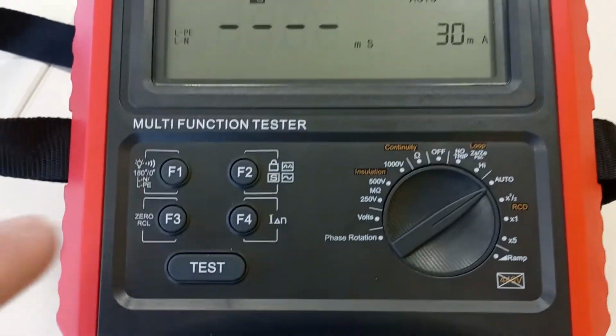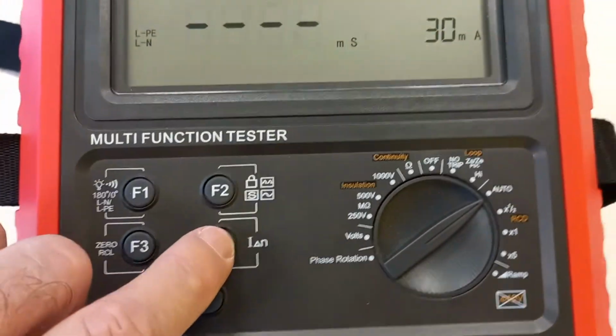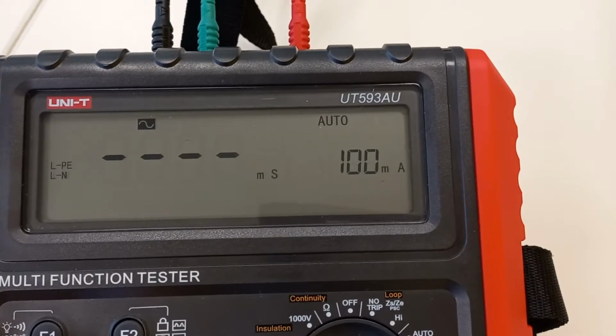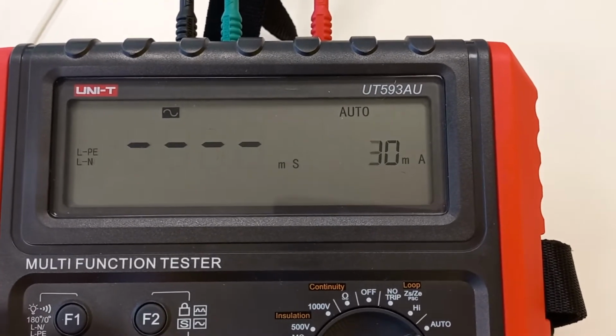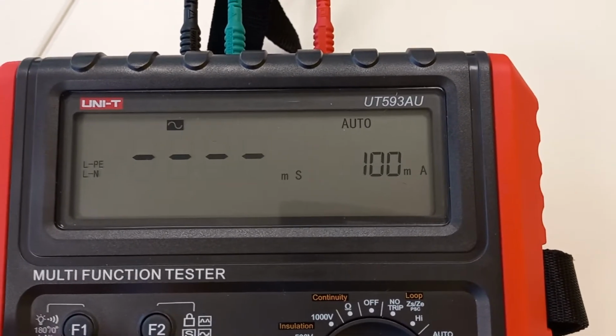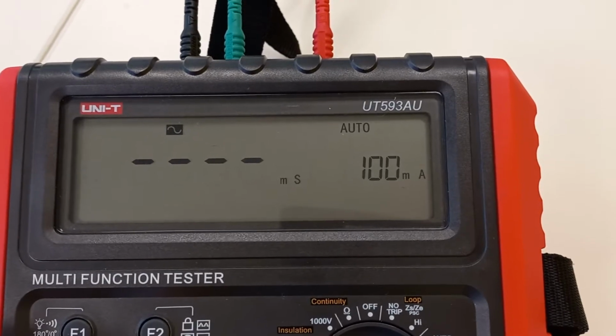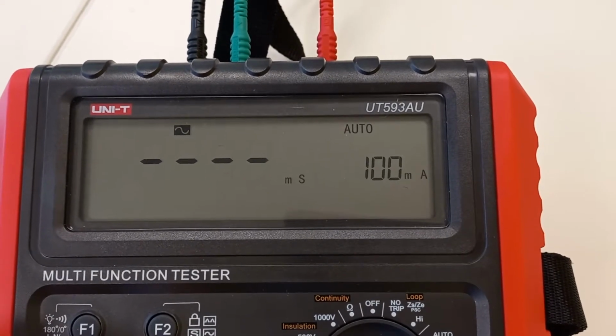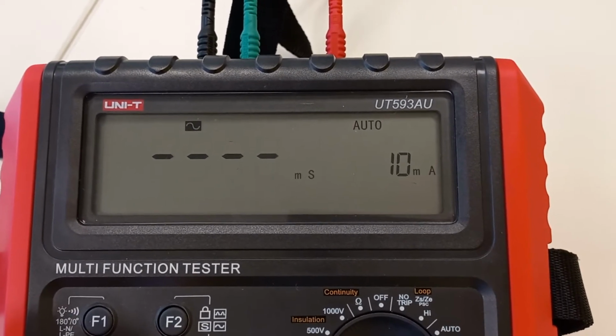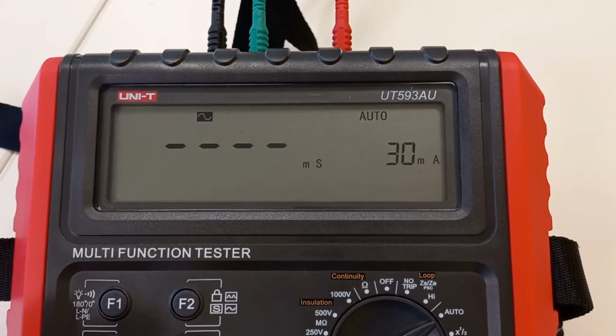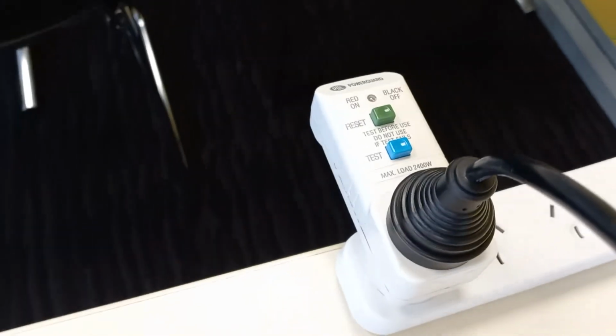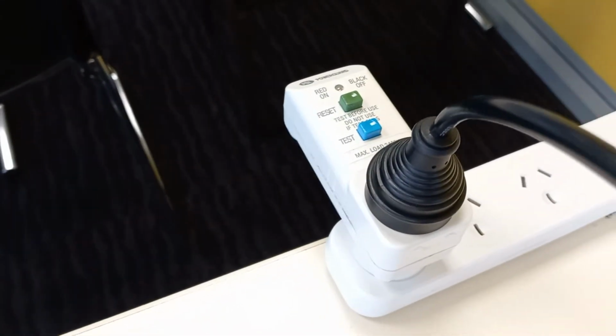First thing we need to do is, down here on F4, set up the current for our test: 10 milliamps, 30 milliamps, 100 milliamps for type S RCD. I'm going back to the 30 milliamp setting because this one is a 30 milliamp sensitivity RCD. It's a portable RCD, very popular.